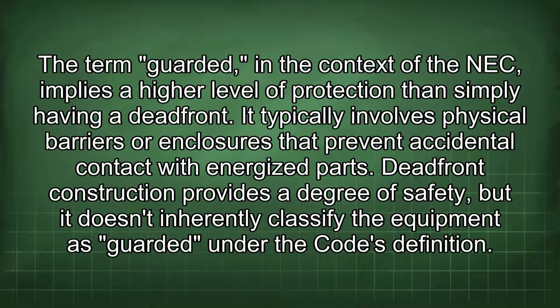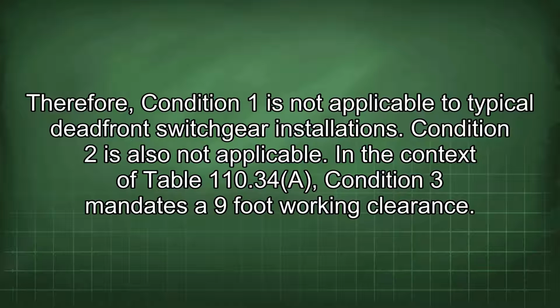The term guarded, in the context of the NEC, implies a higher level of protection than simply having a dead front. It typically involves physical barriers or enclosures that prevent accidental contact with energized parts. Dead-front construction provides a degree of safety, but it doesn't inherently classify the equipment as guarded under the code's definition. Therefore, Condition 1 is not applicable to typical dead-front switchgear installations.